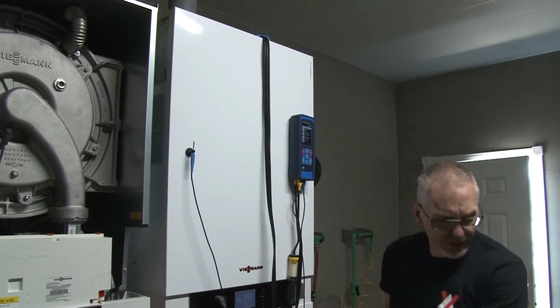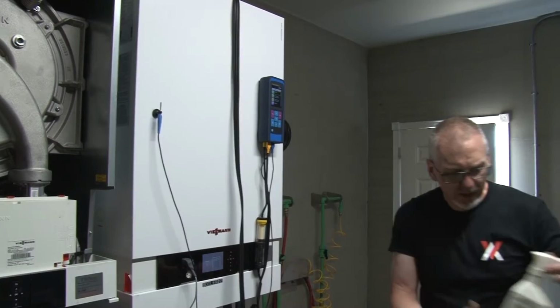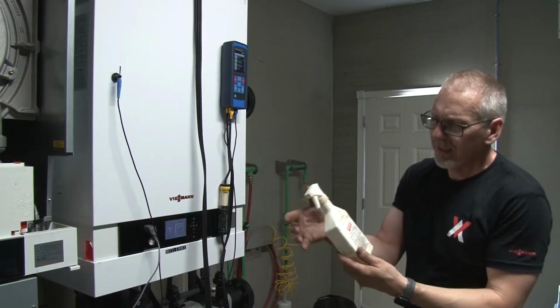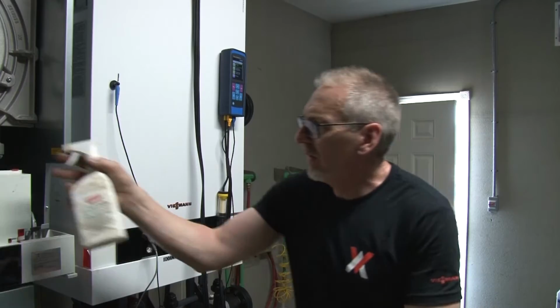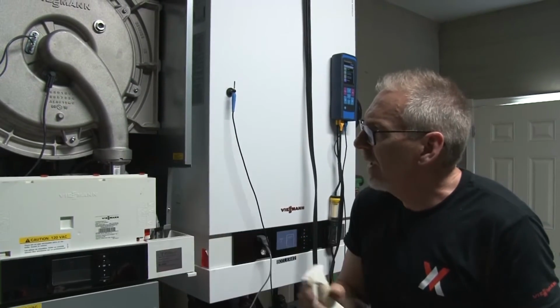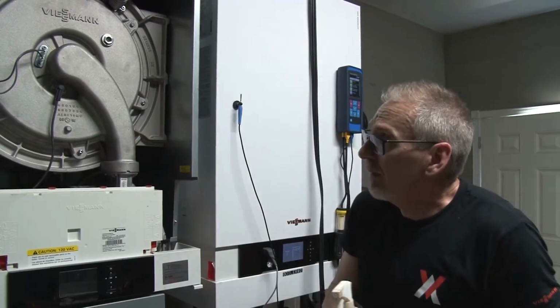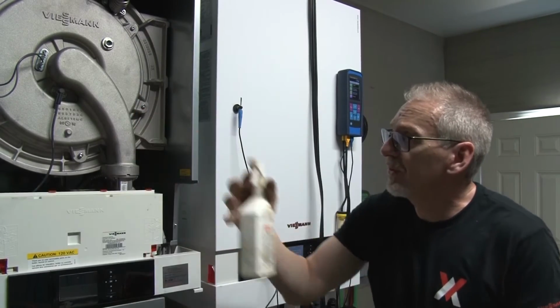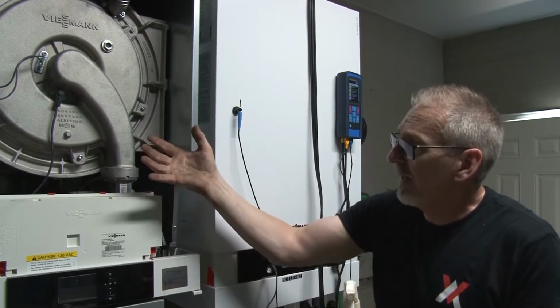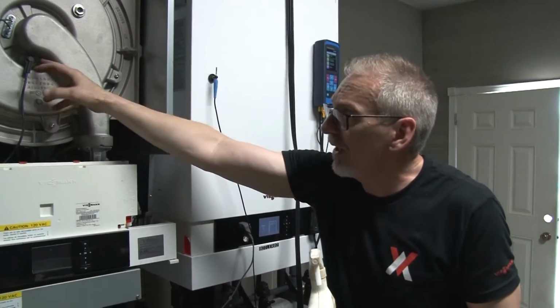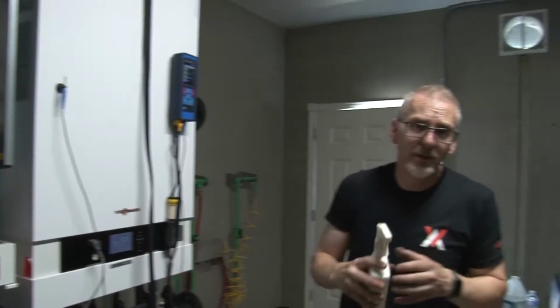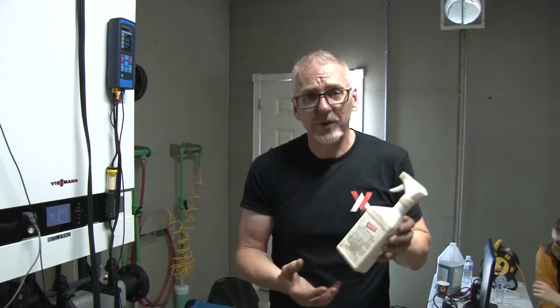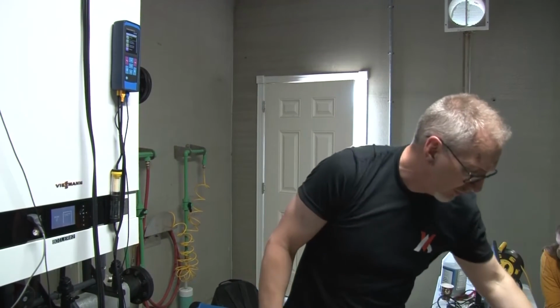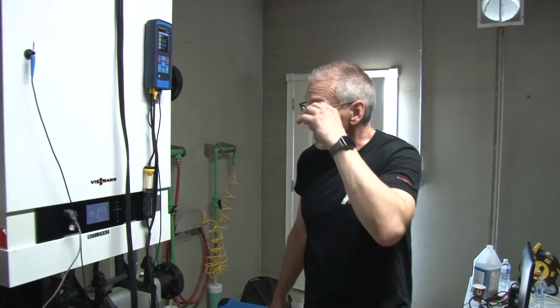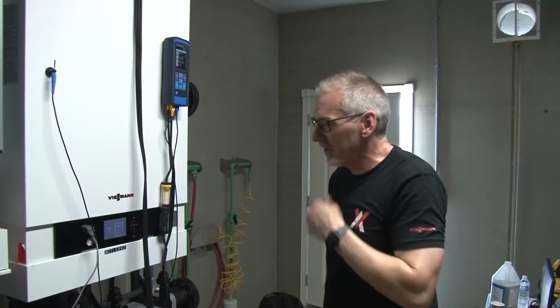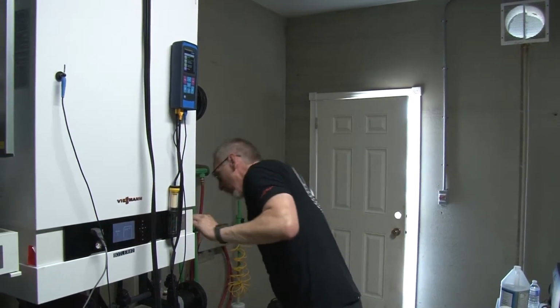We want to do the soap test. So we've got some soap tests here. Basically, all of the areas that I've removed, I had a little area around the gasket here, I want to spray that. The bolts here in this area, spray it with some soap. And when the burner goes to fire, that fan pressure is going to make sure that if we see bubbles there, we need to tighten that stuff up, make sure there's going to be no issues with that. So a leak detector is always something you need to have in your toolkit whenever you're doing any type of service. Once you get all that stuff established, what we can do now is fire these boilers.